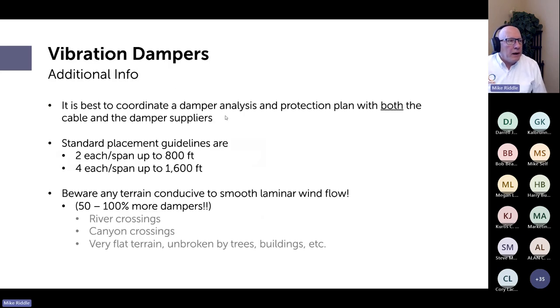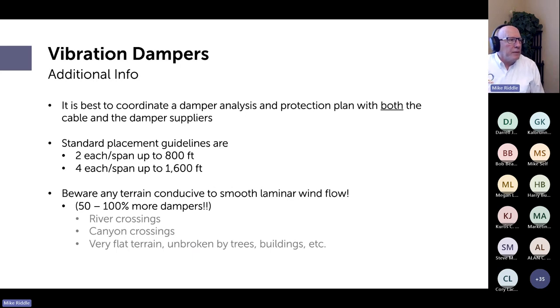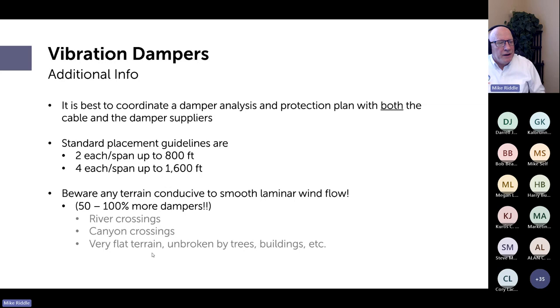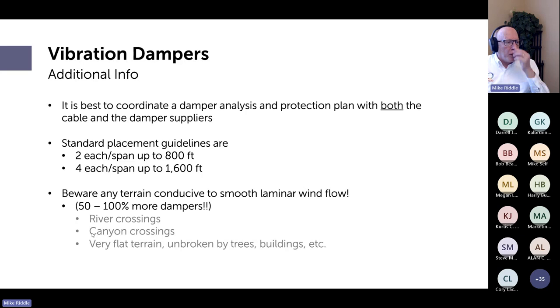It's always a good idea to have the cable supplier and accessory supplier work together on the vibration protection plan. In some cases — river crossings, canyon crossings, or very flat and open terrain — you should consider using 50 to 100 percent more dampers. Consult both the damper and cable suppliers for those situations.